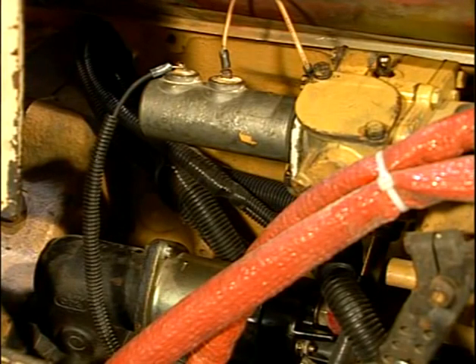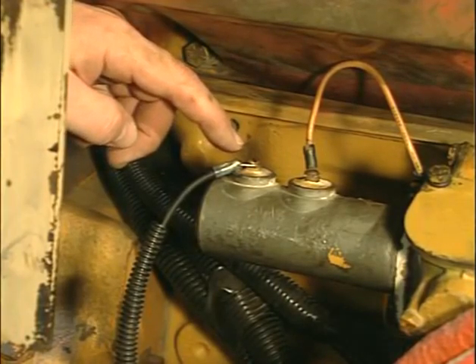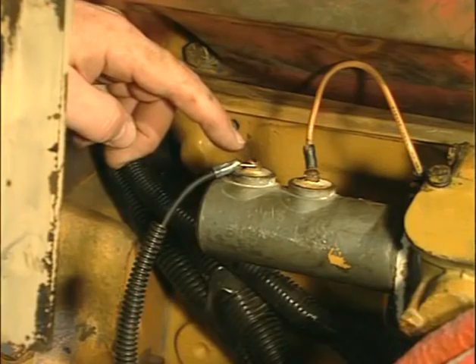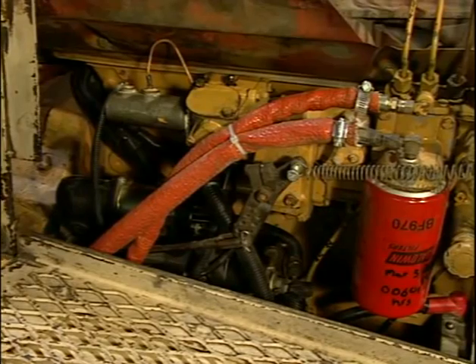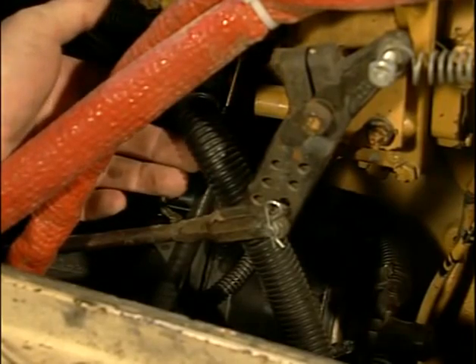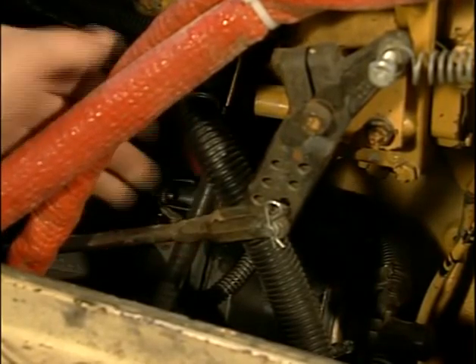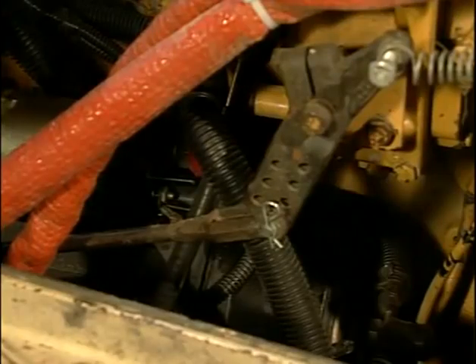The new regulation will require each ungrounded conductor to have insulation compatible with the impressed voltage. The insulation materials must be resistant to deterioration from engine heat and oil. The ungrounded positive lead on this solenoid needs additional insulation. All wiring must have adequate mechanical protection to prevent damage to the cable that might result in short circuits. In addition to mechanical protection, wiring must be separated from sharp edges and corners where there is a possibility of damaging the wires and cables. In this case, the fuel linkage could eventually cause damage to the wiring.